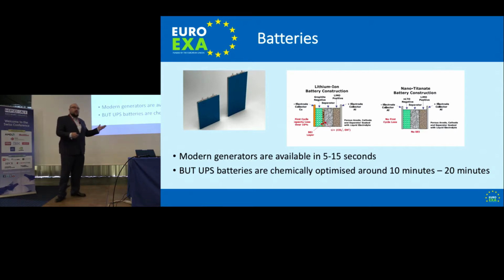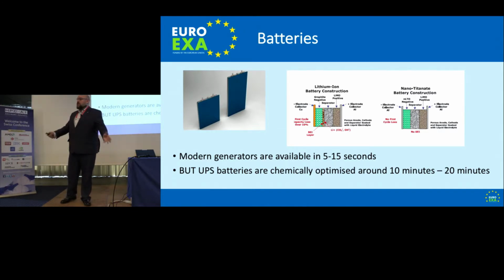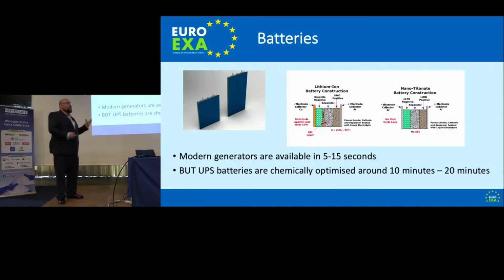Well, saved by a new technology: lithium-ion titanate batteries allow you to discharge 8 times as fast. So instead of 10 minutes, we're between 1 and 2 minutes. That's more than enough time for the generator to get started, warm up, and start dumping power into the system, keeping everything going in a power cut event. So we've looked at lithium-ion titanate technology, which is being deployed into the cabinet attached to that bus bar. No conversion. It'll trickle charge one way, and it will fast discharge the other.